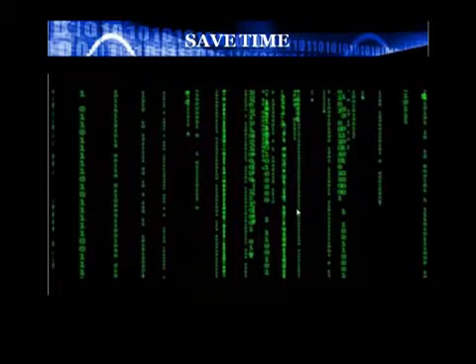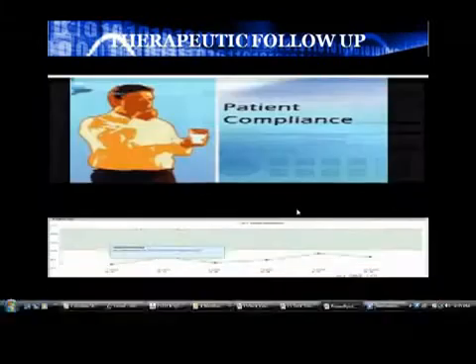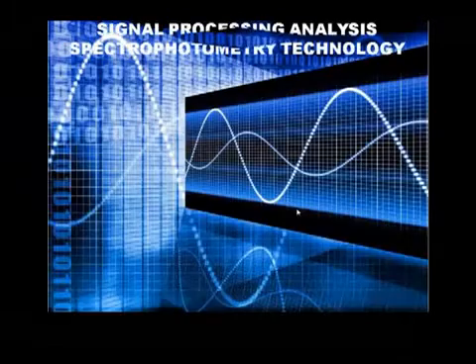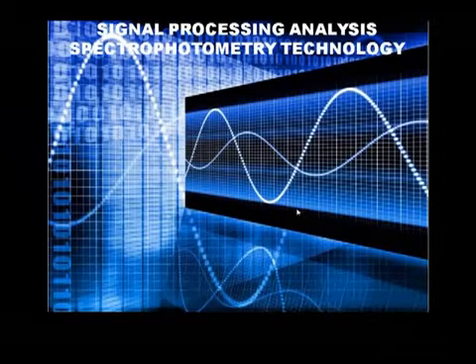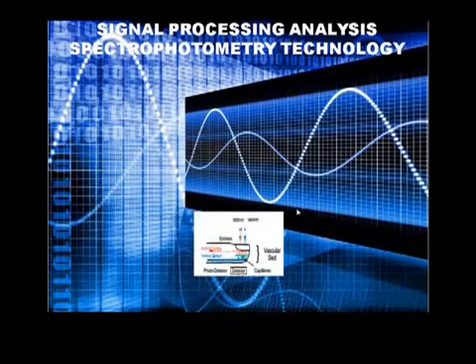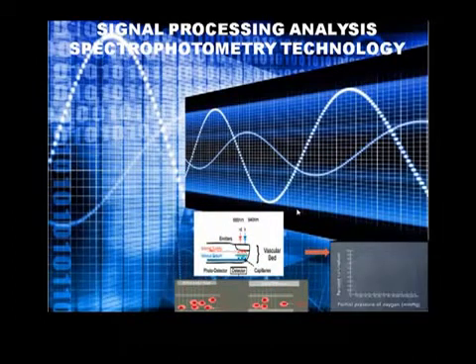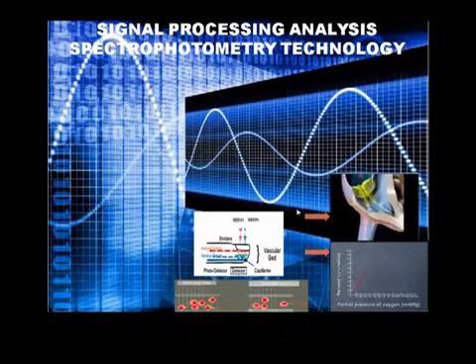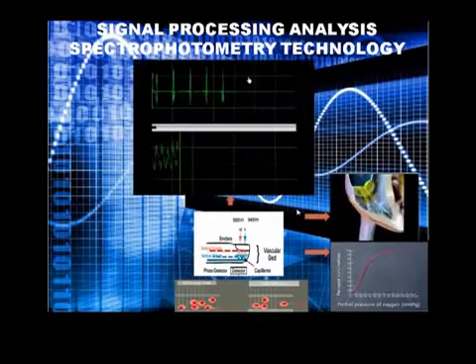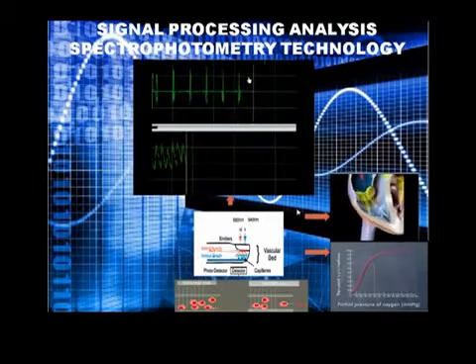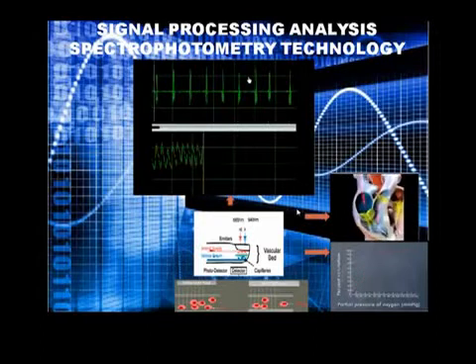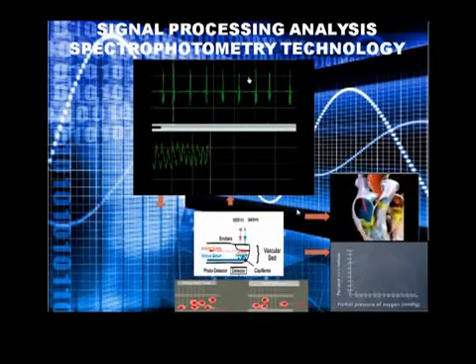Nowadays practitioners are in the same position as were accountants before the adding machine. For signal processing analysis using spectrophotometry technology, the pulse oximeter displays the SPO2%, vascular waveform, and heart rate. The photoelectrical plethysmography is the signal processing analysis of the waveform output of the oximeter and provides hemodynamic indicators.